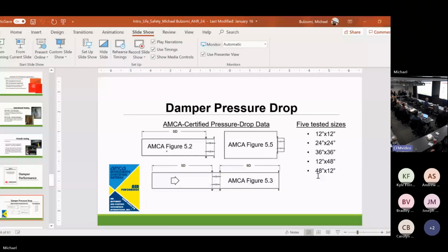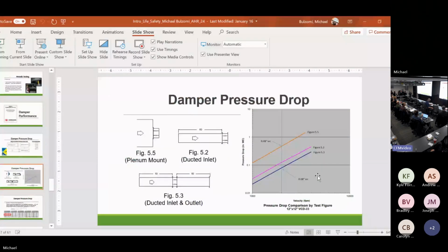Anyway, pressure drop, very important. Do you guys care about pressure drop of dampers? How many of you have a cheat sheet on your desk that says dampers under 24 by 24, take a 1/10 of an inch pressure drop, and dampers over this size, take that? That is the worst thing in the world. You are completely inaccurate. Completely inaccurate. How I'm mounting the damper has an exponential change in the pressure drop.